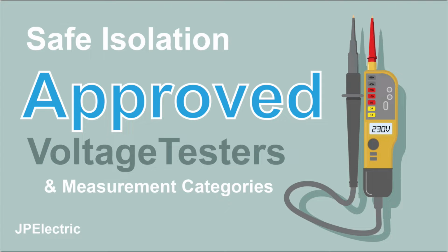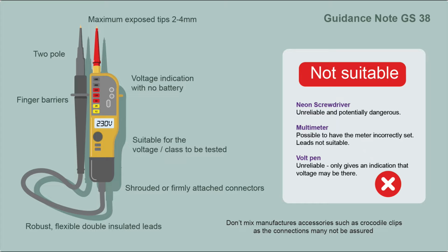Hello there. Right, let's have a look at approved voltage testers and measurement categories, and we'll look at some of the issues you can have when using a voltage tester. The voltage tester is probably your most important piece of equipment because we use it to verify safe isolation, and we can use it to see if there's a dangerous voltage on any equipment we might be working on.